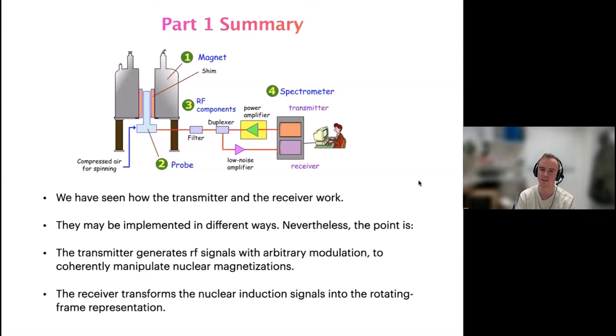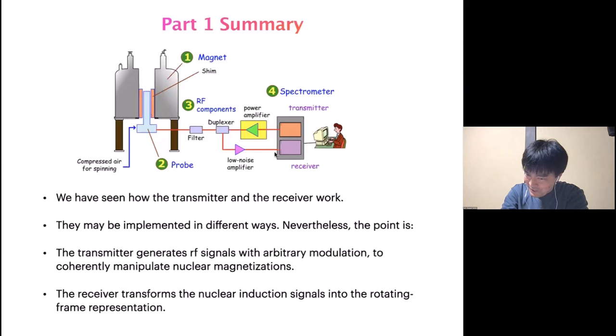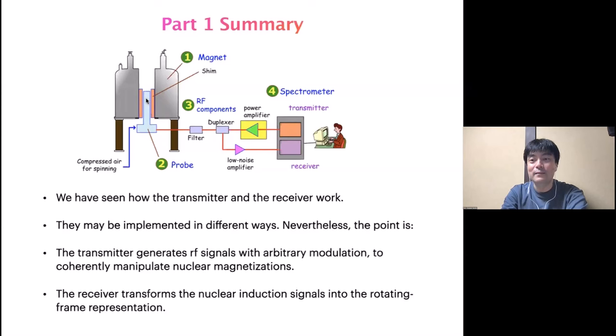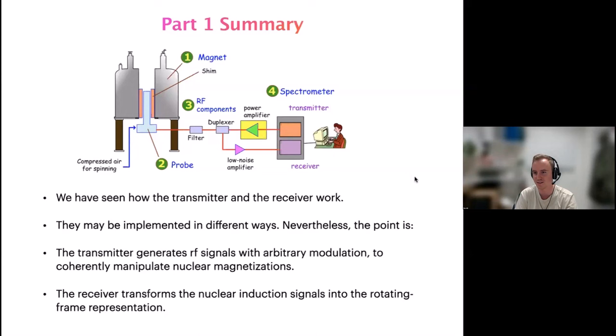A follow-up question: is the low-noise amplifier on the board or closer to the probe? The low-noise amplifier is outside the scope of the spectrometer. You need to use a good LNA because it almost entirely determines the overall signal-to-noise ratio for a given magnetic field and probe quality. Once the signal is strong enough, RF noise from outside is also less important.